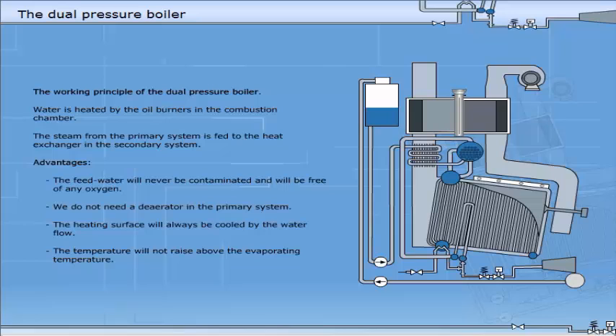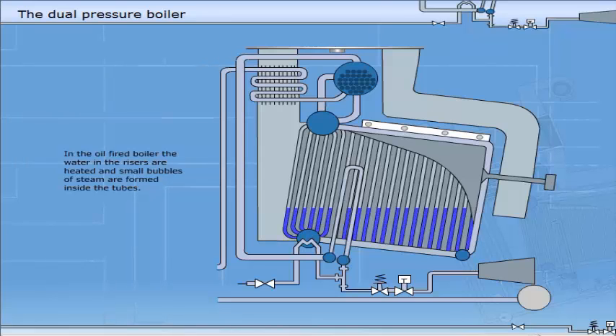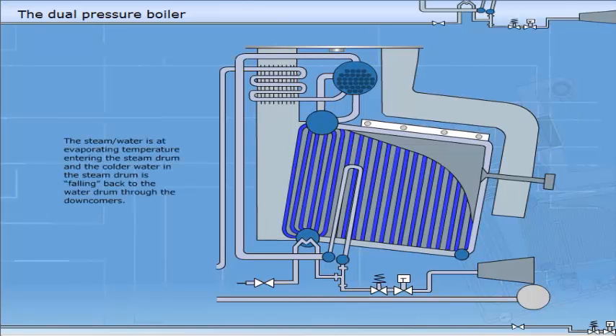This will reduce possible deposits on the heating coil in the secondary steam drum. In the oil-fired boiler, the water in the risers is heated and small bubbles of steam are formed inside the tubes. The steam-water mixture, at evaporating temperature, enters the steam drum, and the colder water in the steam drum is falling back to the water drum through the downcomers. This circulation will continue as long as we are firing the boiler.